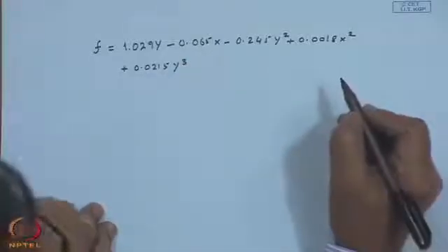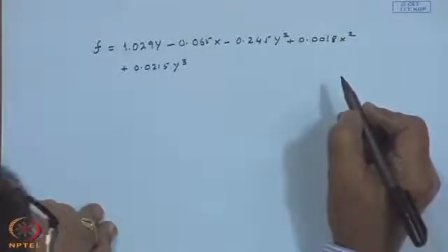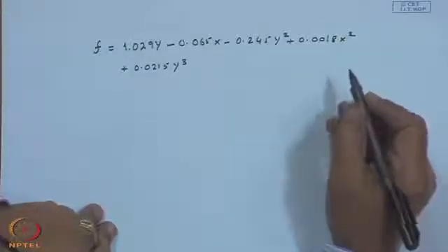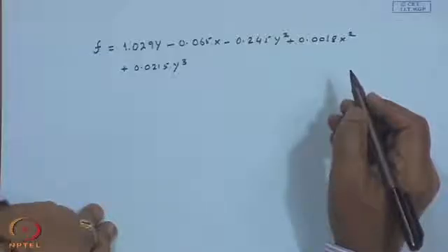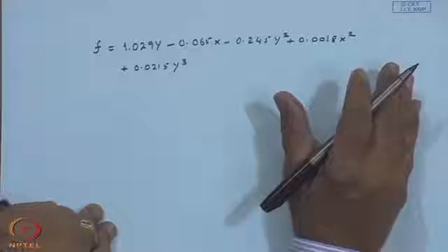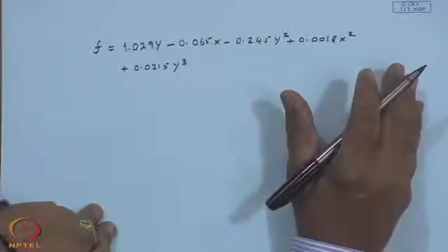So, you will notice the remarkable similarity of the correlation of the liquid based systems to that of the air based systems, which is not surprising. They give comparable performance, except when x and y are a bit too large, either because of non-standard storage or non-standard flow rate, etcetera.